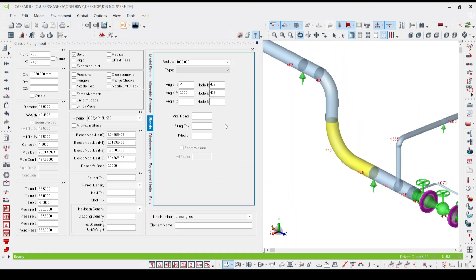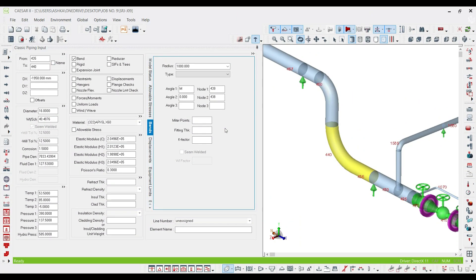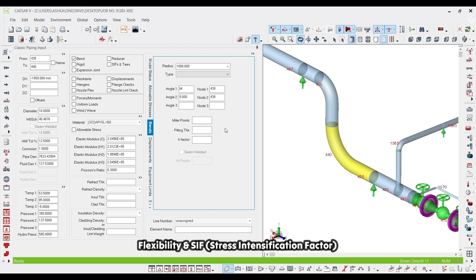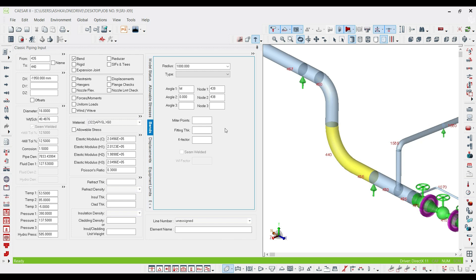The next part is miter point. When you're going to use a mitered bend elbow in your piping system, you have to specify the number of cuts, because in this way, by having the number of cuts and the direction change value, the software can calculate the flexibility and the SIF or stress intensification factor around your elbow.